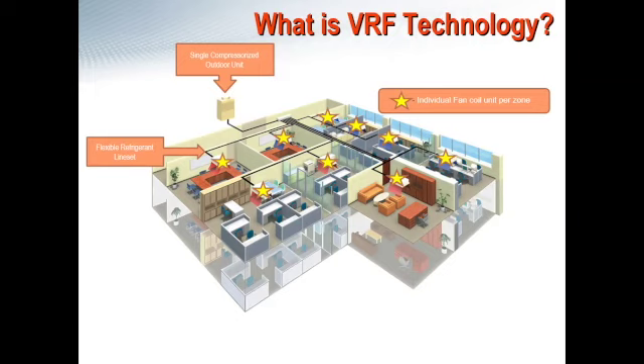that we're going to have an individual fan coil unit in every zone, but the way we like to think of VRF technology is as a zoned solution. We're going to get into a little bit more how that zoning works, how it can be applied further into the presentation. But one thing I want you guys to take away right off the bat is that VRF technology is about providing the correct amount of cooling or heating to satisfy the load in any given zone.